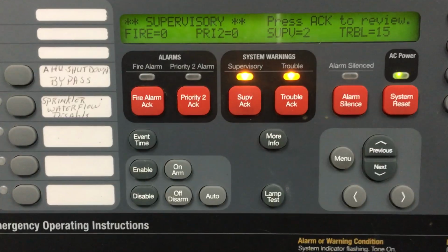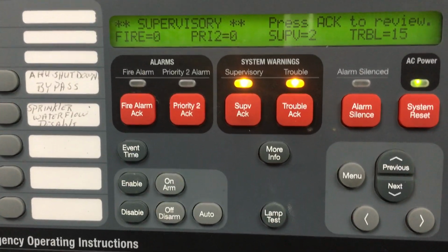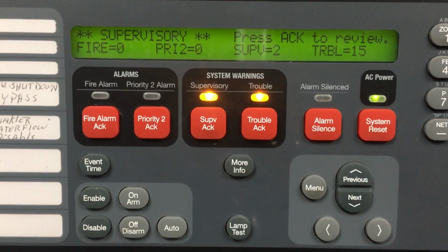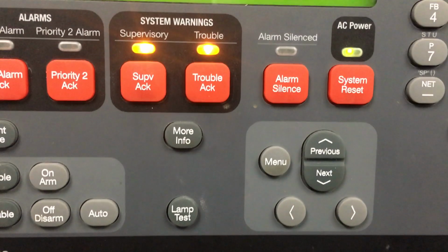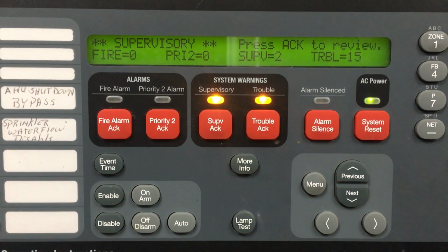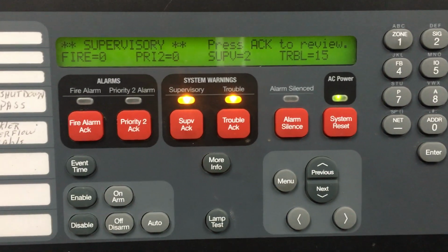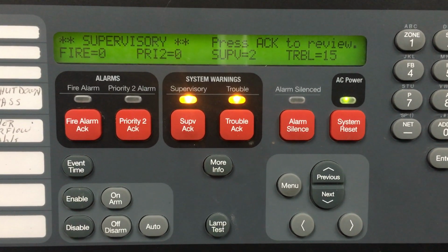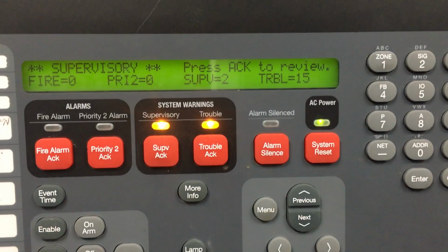Okay, today we have had a damaged pull station and we did not have one in stock. Unfortunately, when you have an alarm or an event, it locks out the HVAC for everyone in the building. So you have to be able to respond quickly when there's not an actual trouble, fire, or environmental incident.